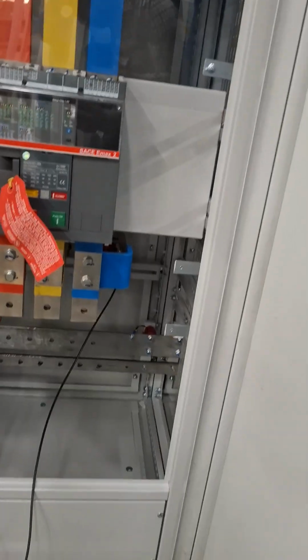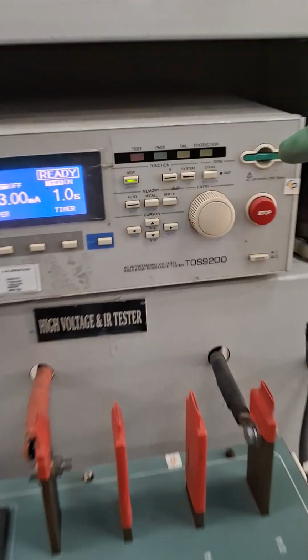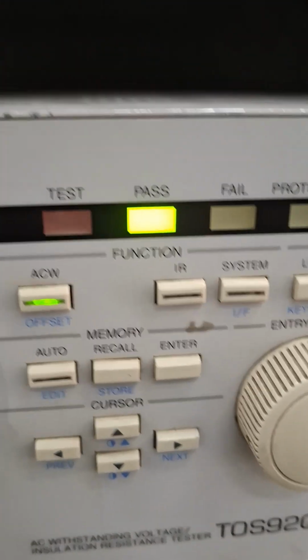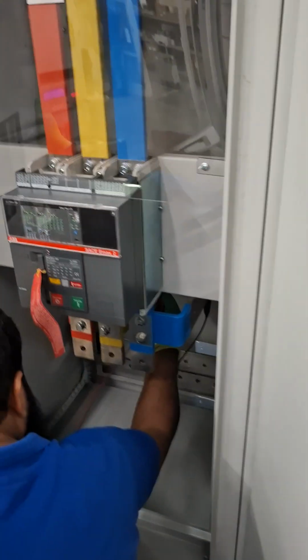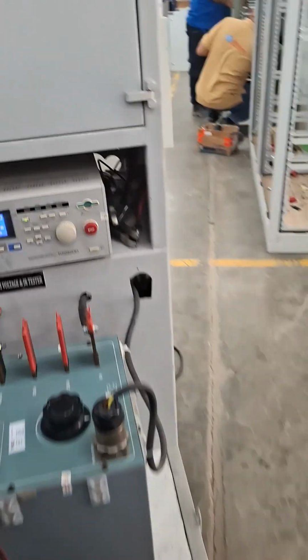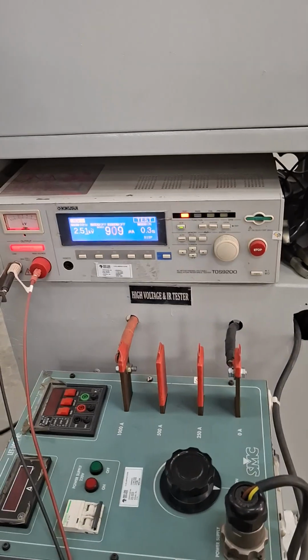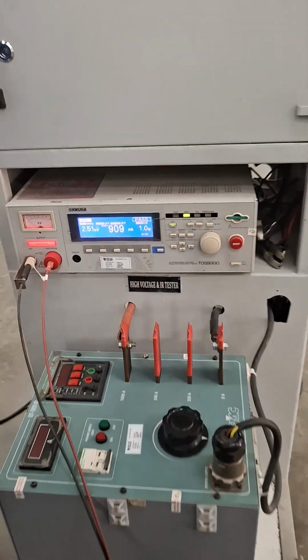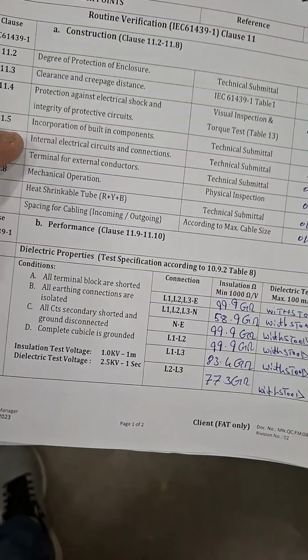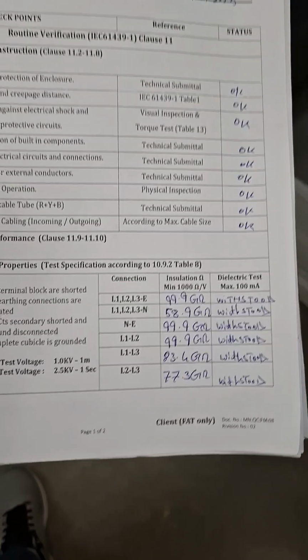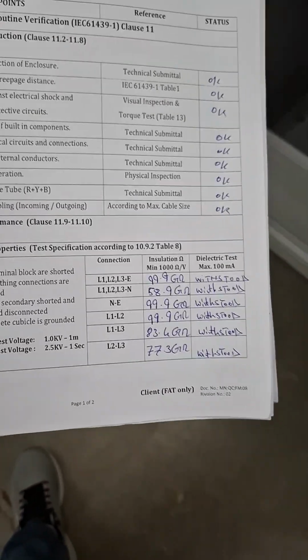Here is the indication. Check phase 1 with phase 3. Okay. As you see, the indication is pass. Okay. If there is any problem inside the breaker, this is also detected. Okay. Our two tests are complete, megger and dielectric test.